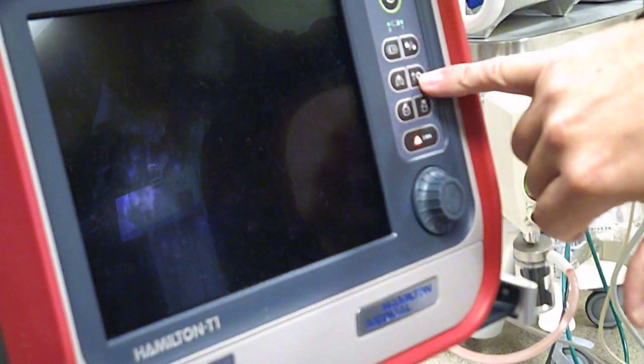So I'm going to make sure he takes a big breath, and I'm going to clamp the tube and then switch over because I don't want to lose any of that recruitment. The arrow up O2 will go to 100% or 1.0 FiO2 for 2 minutes. This is irrelevant because we don't print. And this is if you wanted to use a neb treatment. The neb treatment would plug into here, the yellow port. The huge benefit of using this is you're not going to mess with any of your gases because it's not going to add additional FiO2 on top of it.